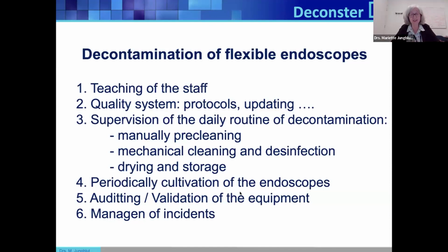So, manual pre-cleaning. As Jill and Bassa told us, the IFU is extended to sometimes more than 100 pages, and we can't know everything anyway at a hospital or at the endoscope area. We have a certain possibility to work. We cannot work through 100 pages each time. So manual pre-cleaning has to be in a standardized way, and we have to always do the same movements, the same steps, one after another. We have to repeat it, and our colleague has to tell us, oh, by the way, you forgot to brush, or by the way, there is another thing on it, there is a little dirt. We have to check on each other.